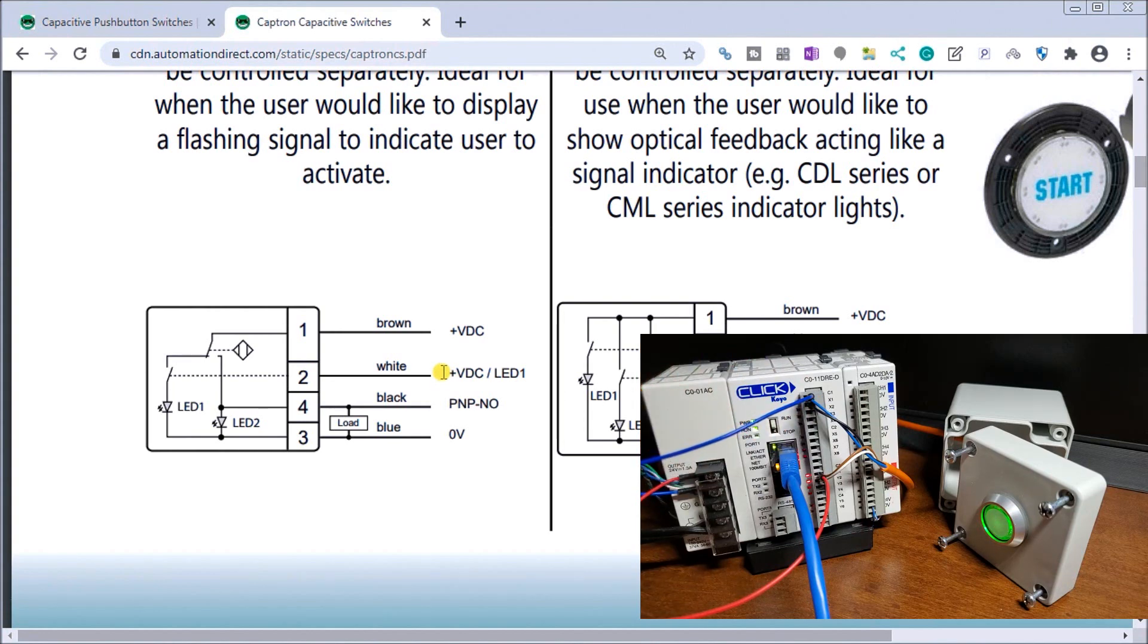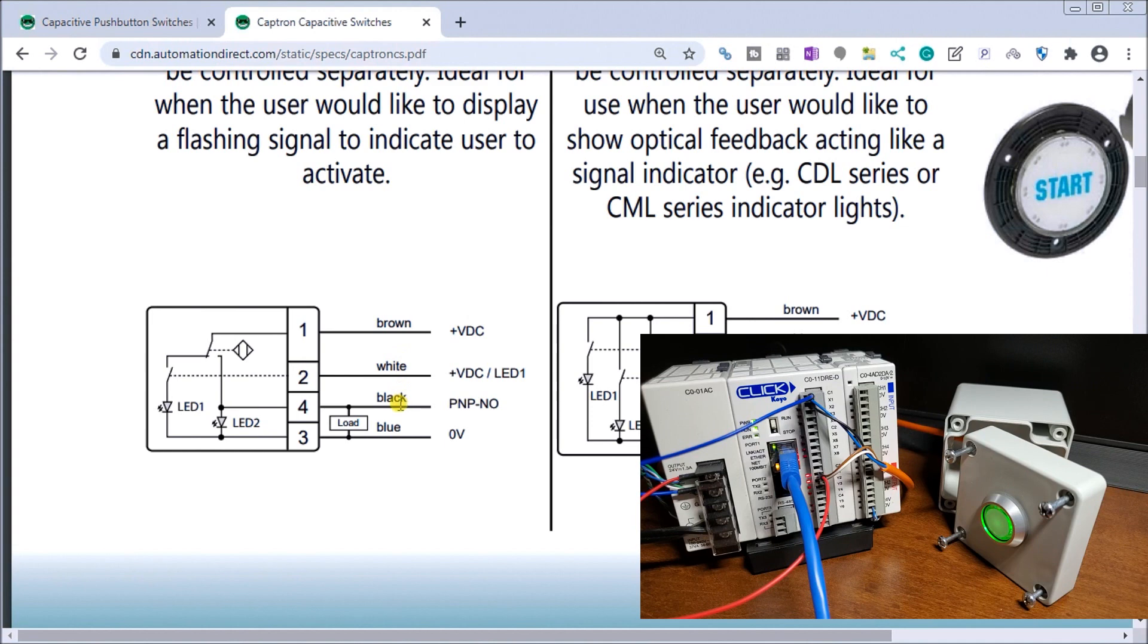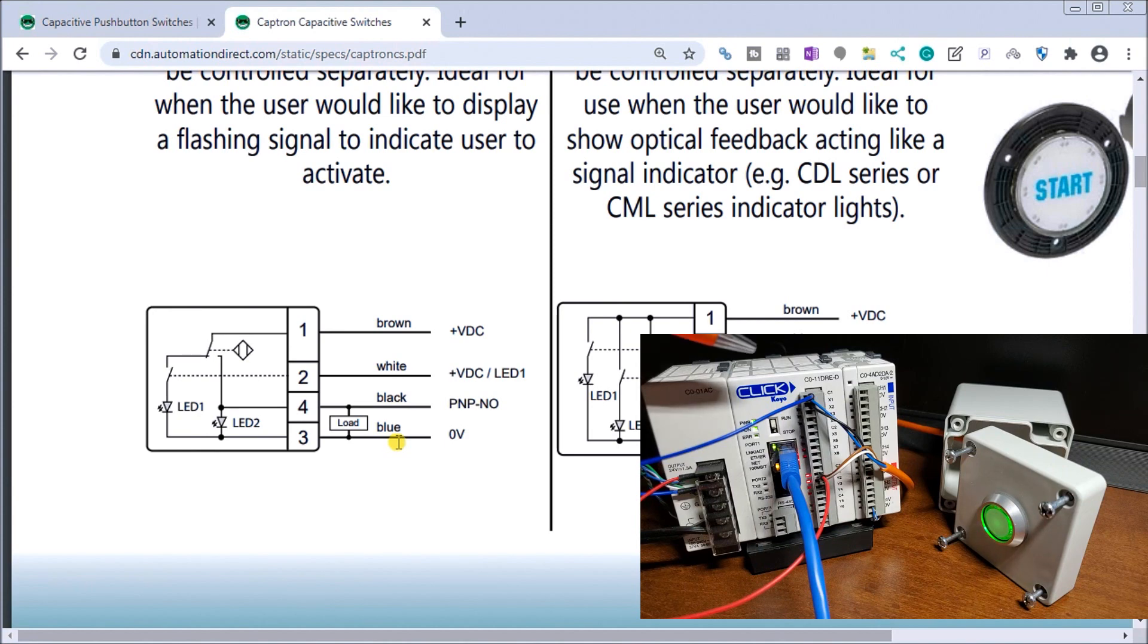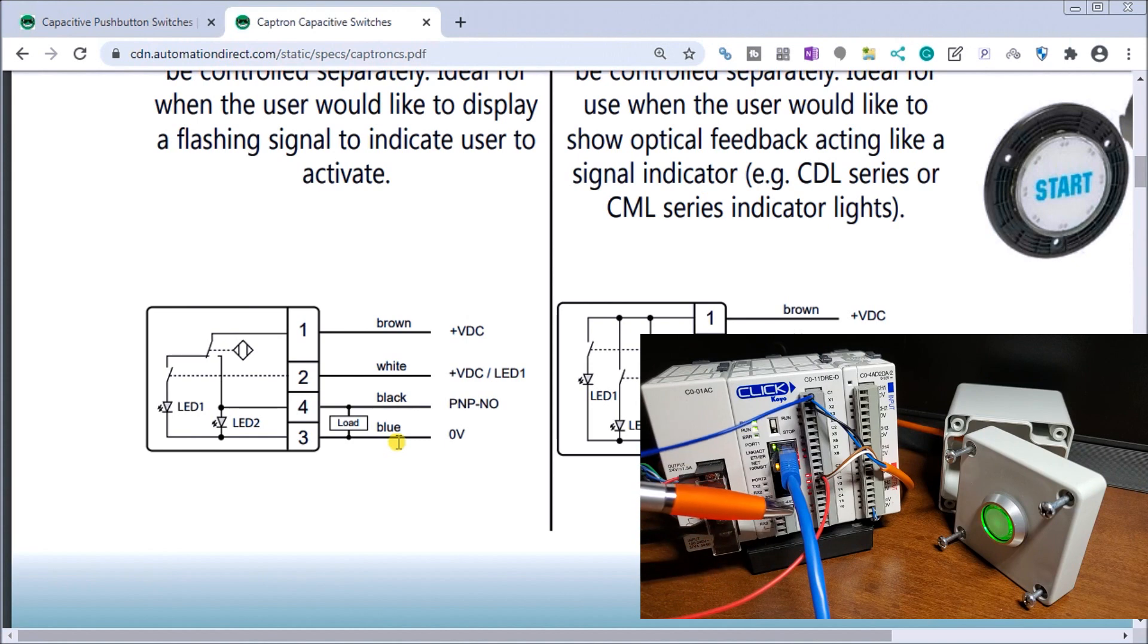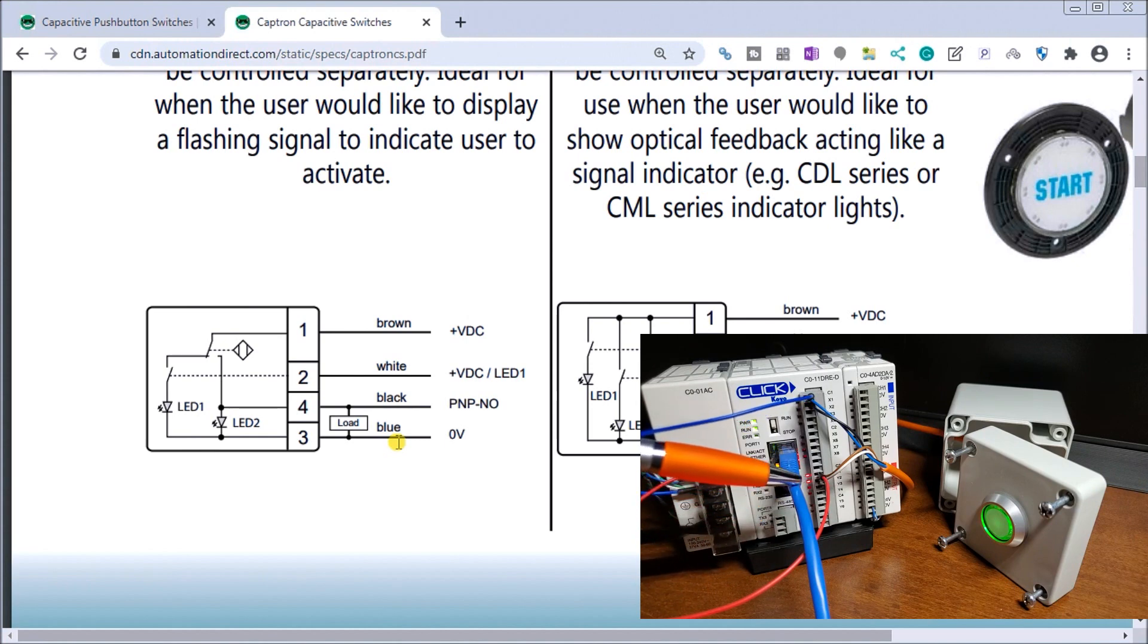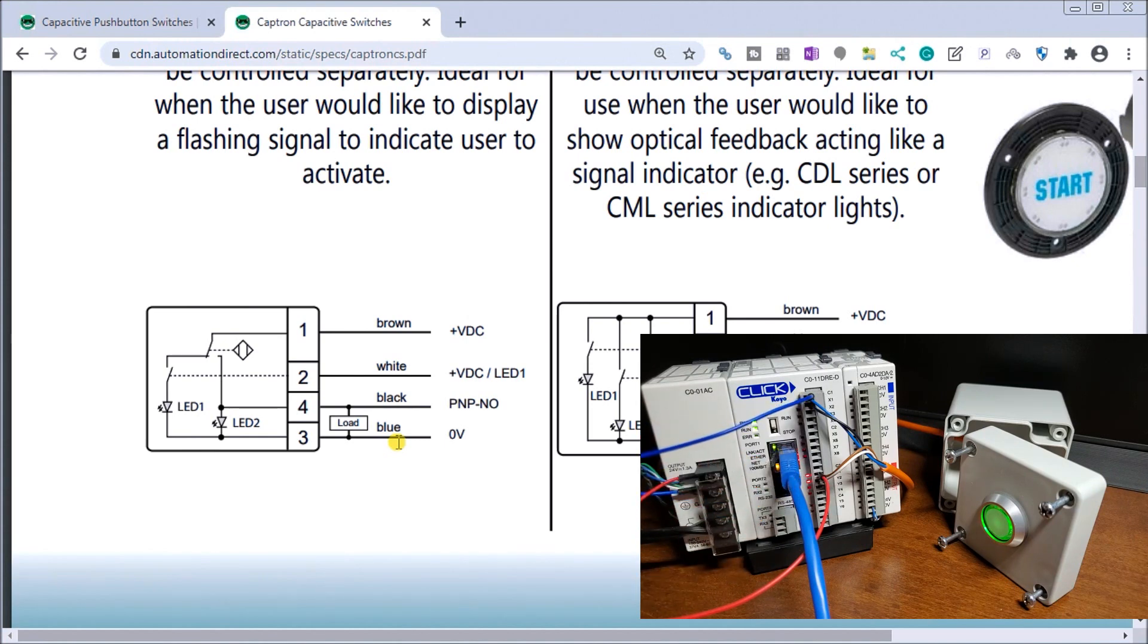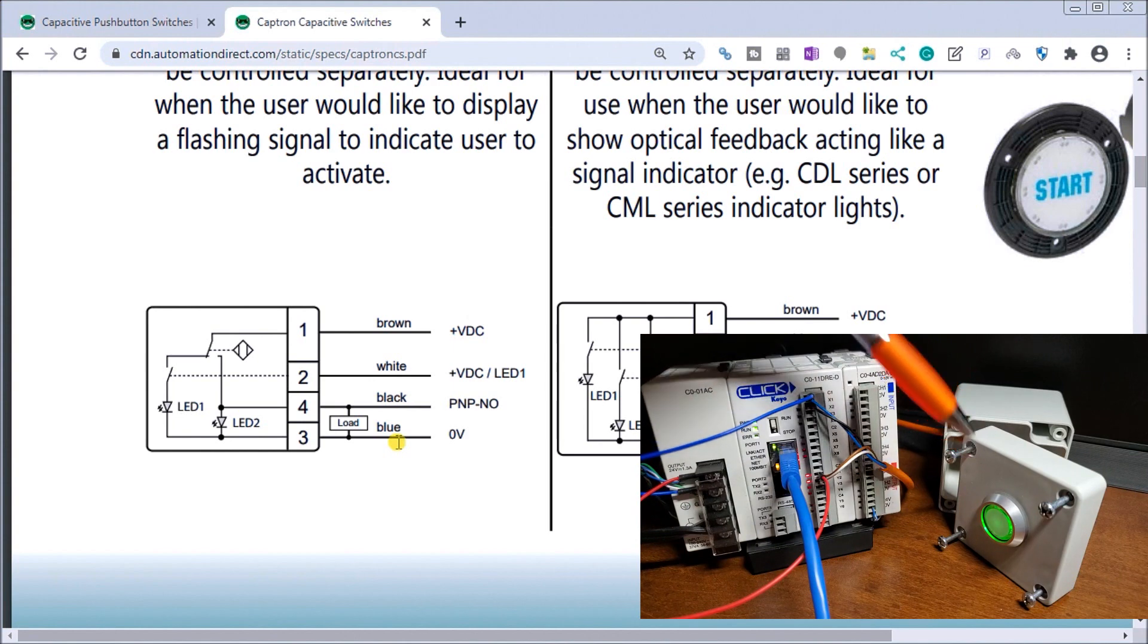So my brown here is connected to my 24 volt, my white wire is connected to my first output, and then I have my black wire going to my first input and my blue wire connecting to zero volts. So that is the diagram that we have. And I've added a second output on the Click Y2, which actually will control what we're controlling with our pushbutton selector switch here.